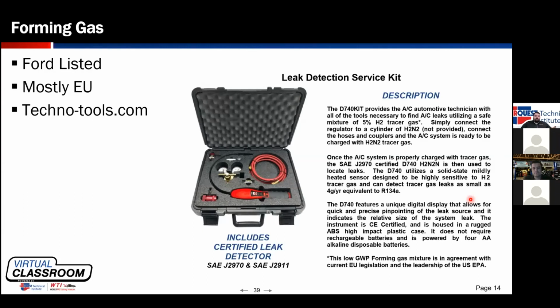The reason why Ford has approved forming gas goes back to European regulations. In the United States, it is currently lawful to charge a system with a charge of refrigerant for leak detection. In Europe, it is not. So if we can't put refrigerant into the system to find a leak, we got to have another way to find a leak. So that's where this came from. You know, for years and years, guys have used nitrogen to find leaks. The problem with pressurizing with nitrogen is, again, detecting it when it leaks. Because this has the trace amount of hydrogen, we now have a detector that can detect the hydrogen. Techno Tools makes this kit, the kit that's pictured. I believe Robinair sells a kit as well.